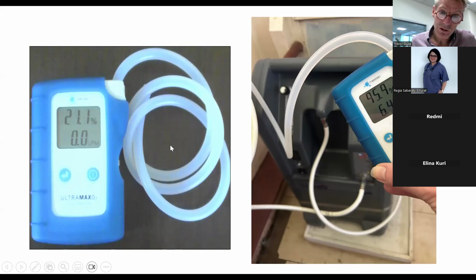So that's this device, this oxygen analyzer is just open to air. There's some tubing there and it's open to air. And so it's 21%, and there's no flow through the tubing. When you hook it up to an oxygen concentrator, as this one is, the concentrator is dialed up to 6.4 liters per minute, and the concentrator is making 95.9 or nearly 96% oxygen. So it's running very well. And this can give you confidence that your oxygen concentrator is delivering the oxygen you want it to deliver. Okay.